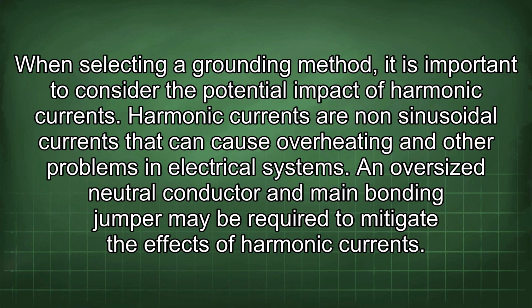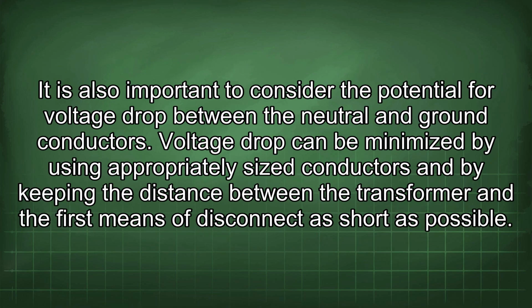When selecting a grounding method, it is important to consider the potential impact of harmonic currents. Harmonic currents are non-sinusoidal currents that can cause overheating and other problems in electrical systems. An oversized neutral conductor and main bonding jumper may be required to mitigate the effects of harmonic currents. It is also important to consider the potential for voltage drop between the neutral and ground conductors. Voltage drop can be minimized by using appropriately sized conductors and by keeping the distance between the transformer and the first means of disconnect as short as possible.